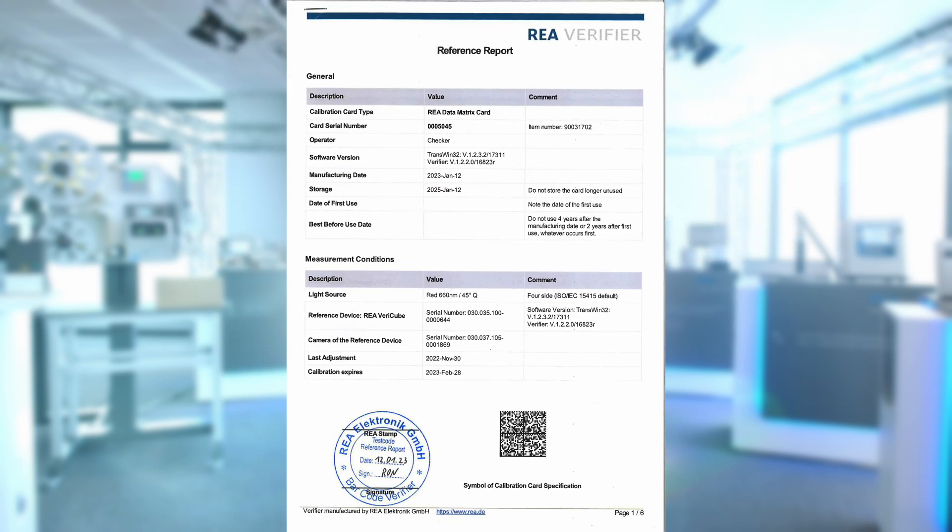For the next step we need the reference report that is included in the folder of the calibration card with the data matrix codes. Recognizable by a round stamp with date and signature on the first page.